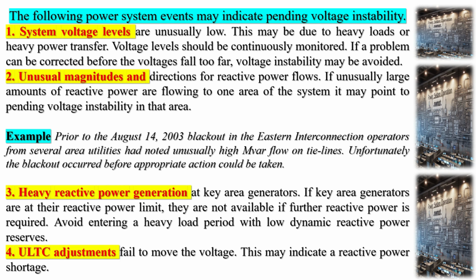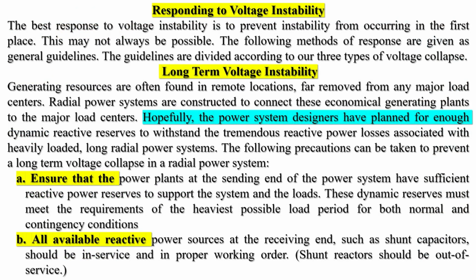Heavy reactive power generation at key area generators. If key area generators are at their reactive power limit, they are not available if further reactive power is required. Avoid entering a heavy load period with low dynamic reactive power reserves. ULTC adjustments fail to move the voltage. This may indicate a reactive power shortage. Responding to voltage instability. The best response to voltage instability is to prevent instability from occurring in the first place. This may not always be possible. The following methods of response are given as general guidelines. The guidelines are divided according to our three types of voltage collapse.